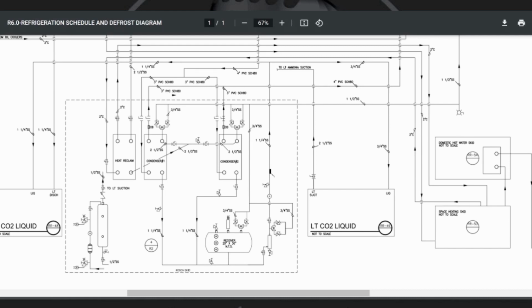And it's close coupled to the compressors. So it's all in the machine room. Yeah, so that's a real trick, maintaining your superheat, making sure you don't grenade that compressor with a whole bunch of liquid. That's correct. I'm assuming you're using some sort of electronic controller and electronic expansion valve on the CO2? Yes, I believe those are Danfoss MKVs. I think. Don't quote me on that. I don't know for sure. That's fine.